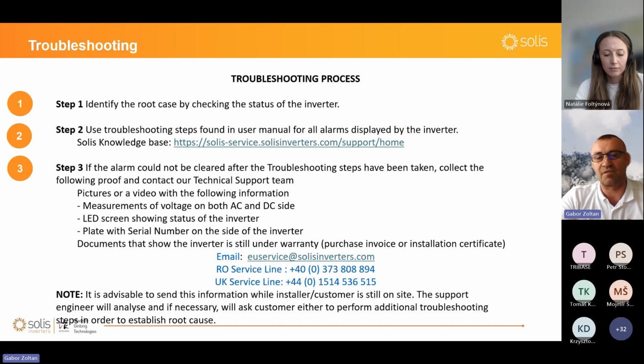If you just send, we have alarm 1028, it's not enough. We need the inverter serial number or the plant number to find the inverter. We need a bit more information about the installation: how many strings are connected, what type of battery is connected, how many inverters are connected, and whether the other inverters have communication or not. So please try to give us as much information as possible.